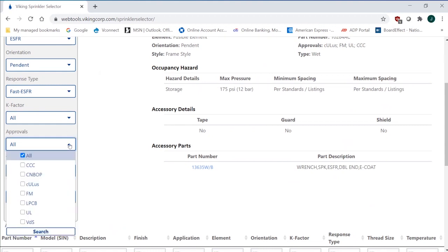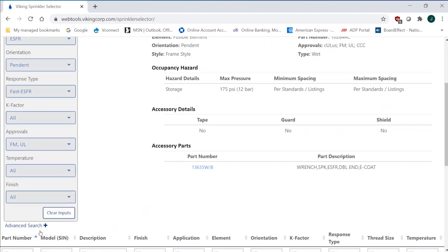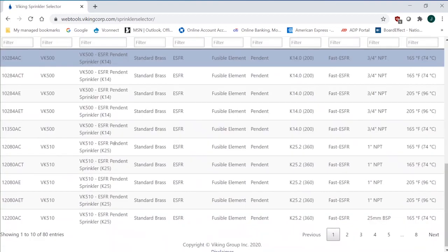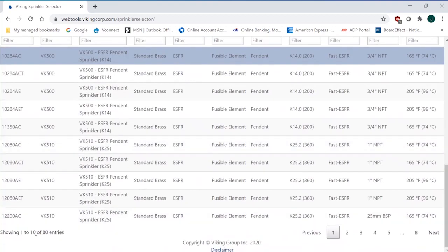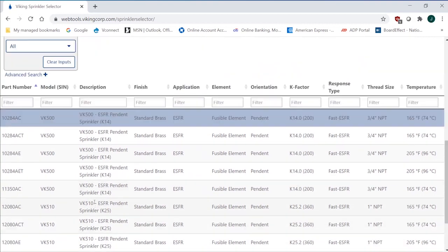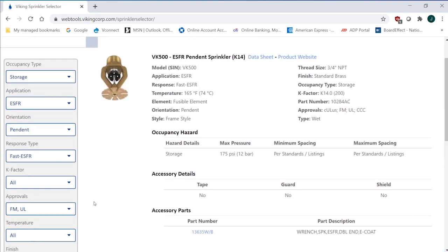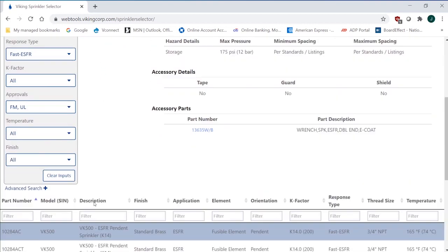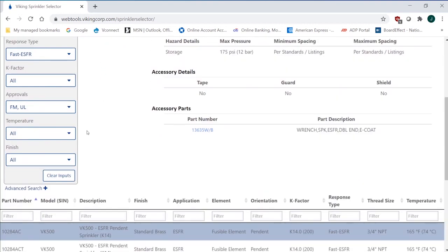K-factor - maybe I don't want to select the K-factor yet. I want to look at approvals. So I want to say, you know what, I really need FM on this one, and I really need UL. Those are my two labs that I need, but it has to be FM compliant. So I'm going to pick that, and you can see that I'm limiting my entries now down to 80 in the ESFR application that I've selected so far.